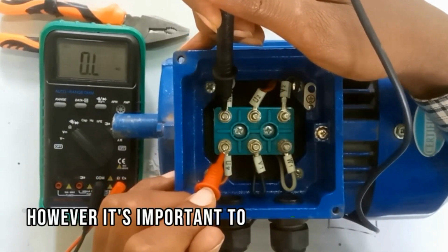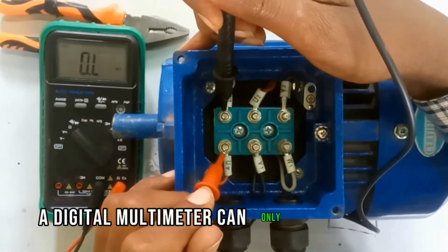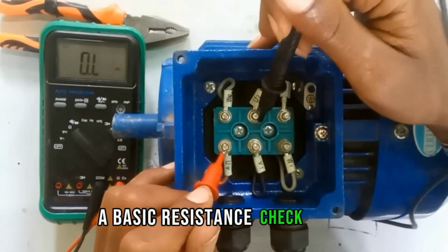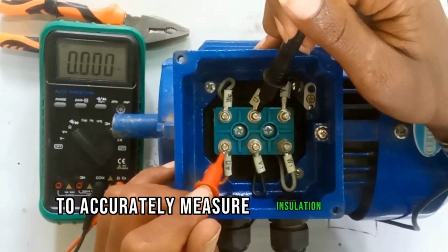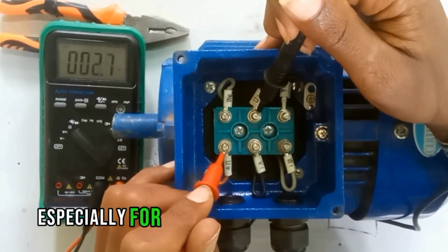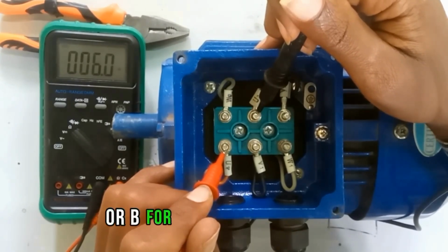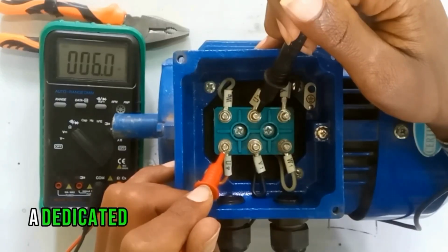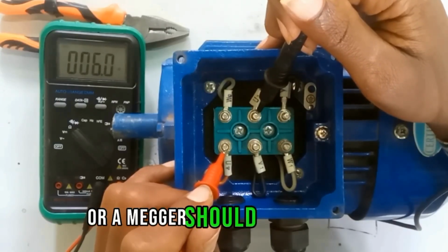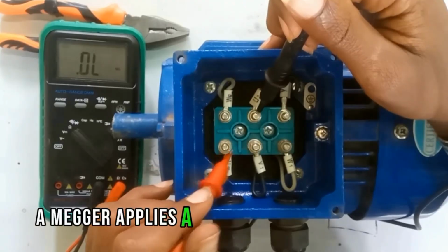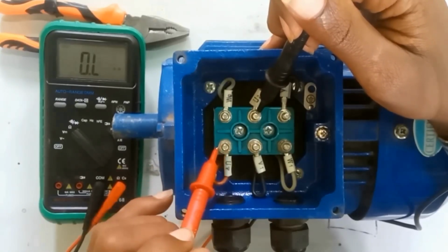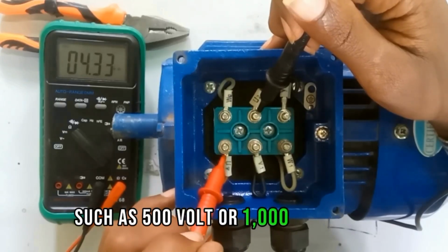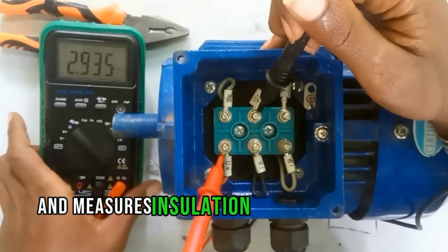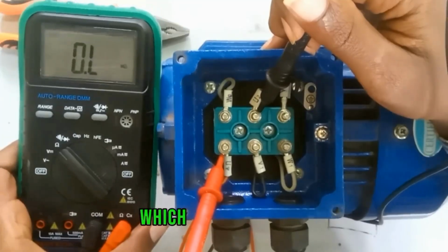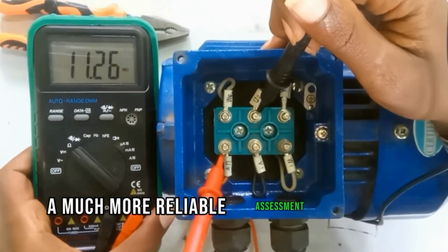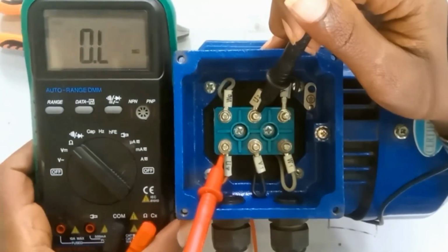However, it's important to remember that a digital multimeter can only perform a basic resistance check. To accurately measure insulation resistance, especially for preventive maintenance or before commissioning, a dedicated insulation resistance tester or a megger should be used. A megger applies a high DC voltage test, such as 500 volts or 1000 volts, and measures insulation resistance in megaohms, which provides a much more reliable assessment of insulation quality.